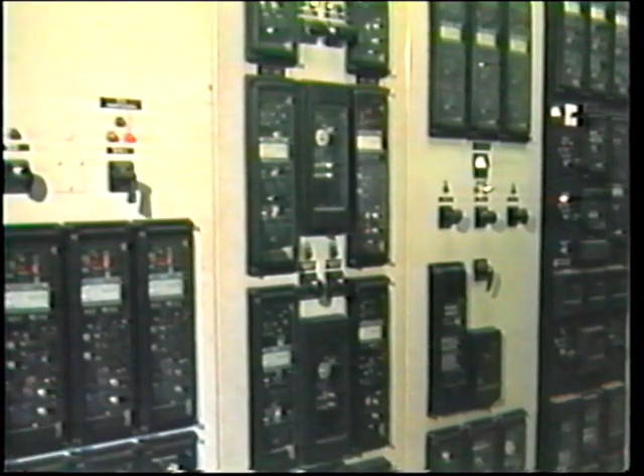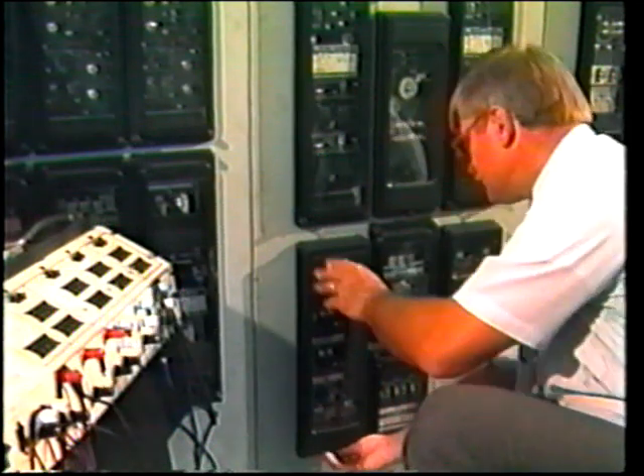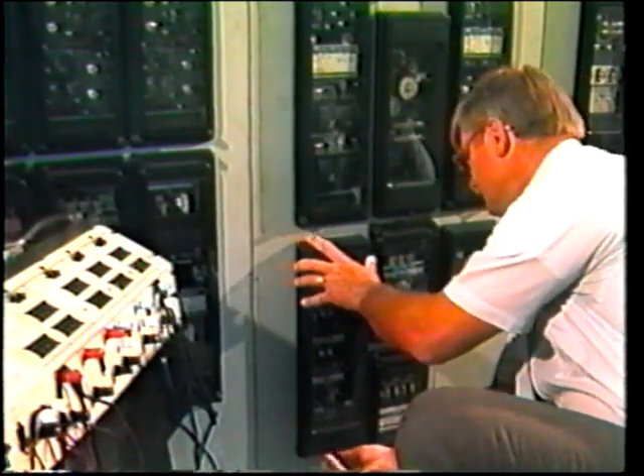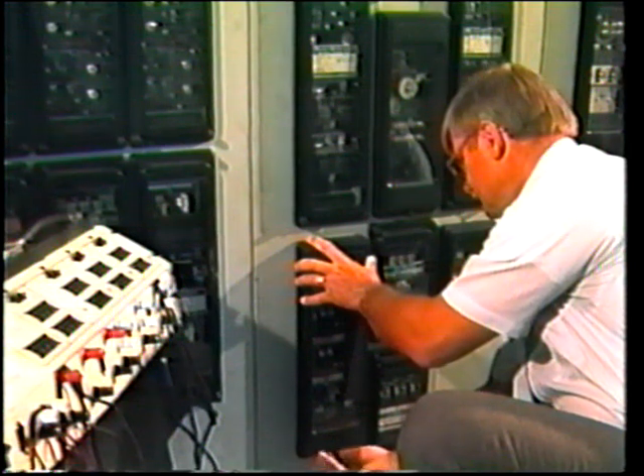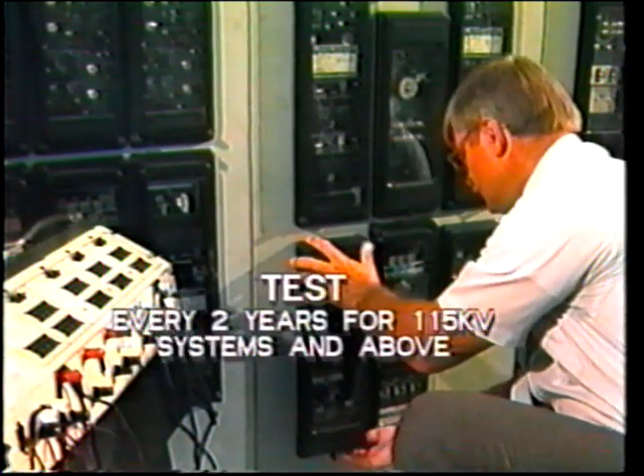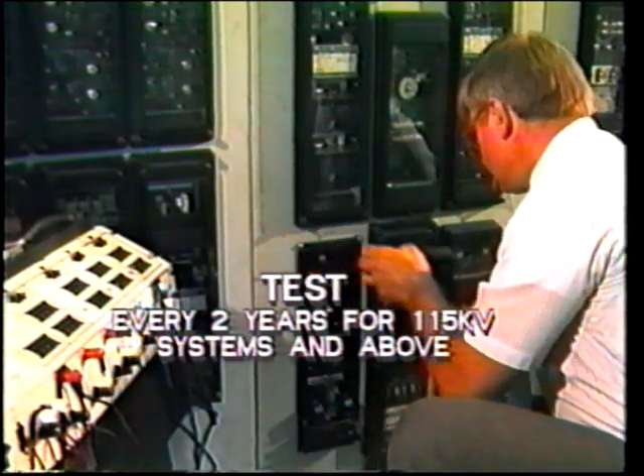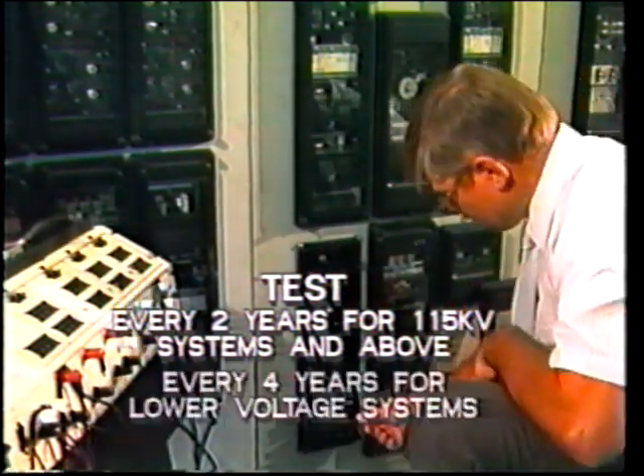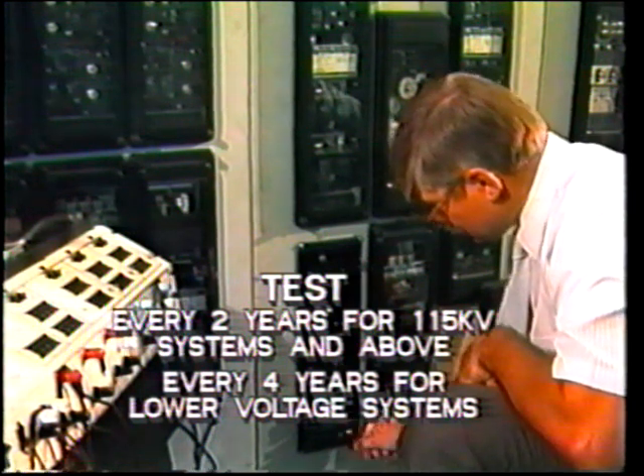Of course, we could show many more examples of this type of problem, but it is fairly obvious that not all protection equipment stays in its as-new condition. Small items of equipment wear out. Settings may drift in certain instances. Stray ground currents may infiltrate the circuit. Insulation may deteriorate, and so on. For this reason, it is essential that routine testing of protection schemes be carried out at standard intervals of time. In most companies, the time period is every 2 years for 115 kV systems and above, and every 4 years for lower voltage systems.